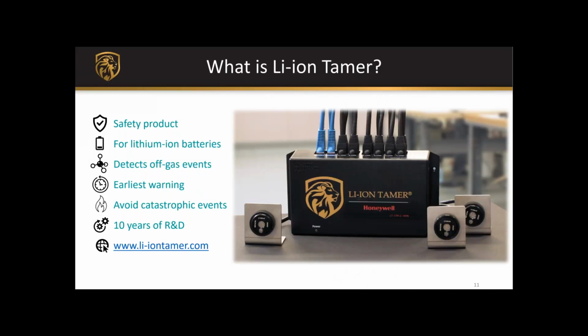We'll start with a basic question: what is Li-ion Tamer? At its core it's a safety product designed specifically for lithium-ion batteries. It works by detecting off-gas events that are emitted prior to thermal runaway, thus providing the earliest warning of any detection system that something's beginning to go wrong in the battery system.